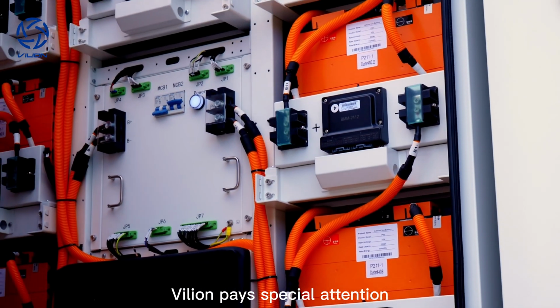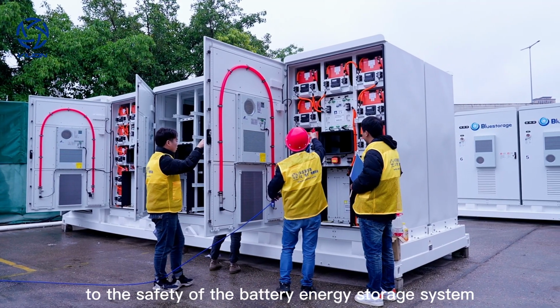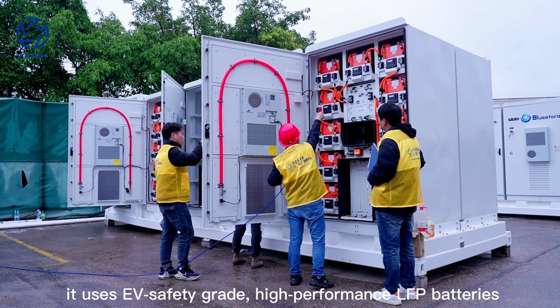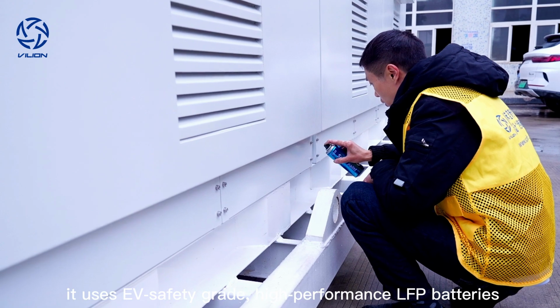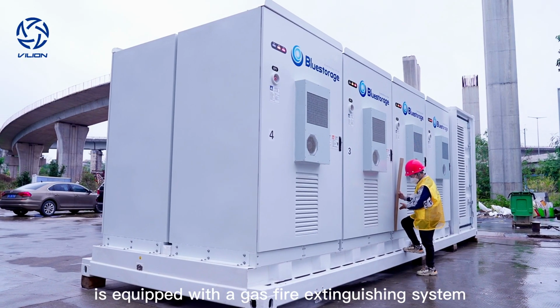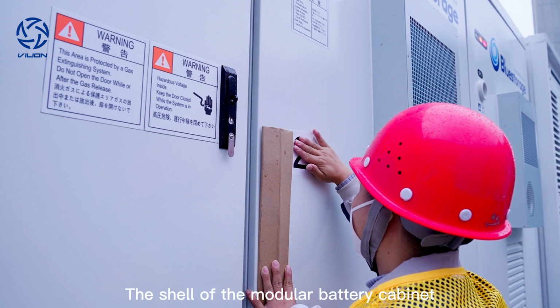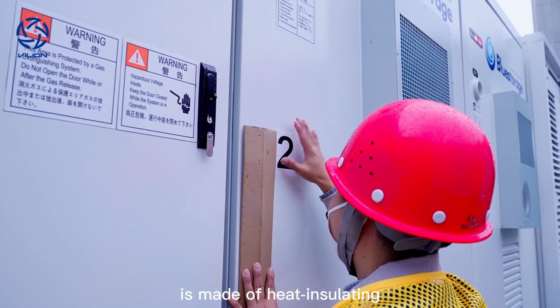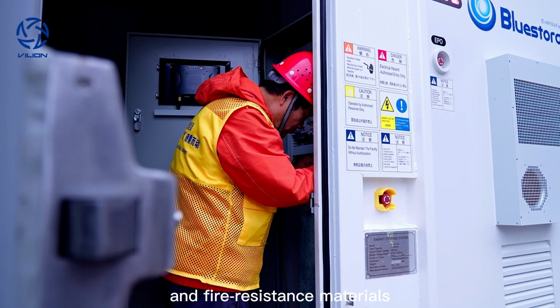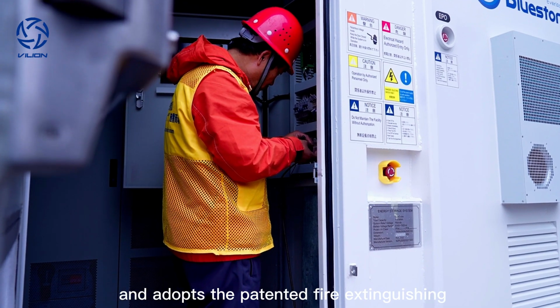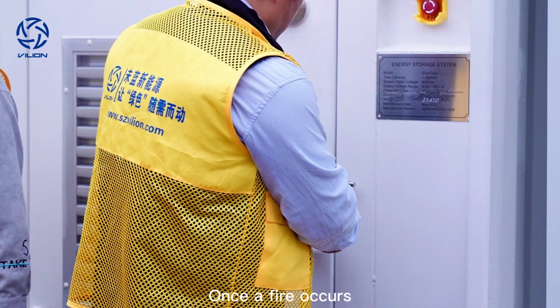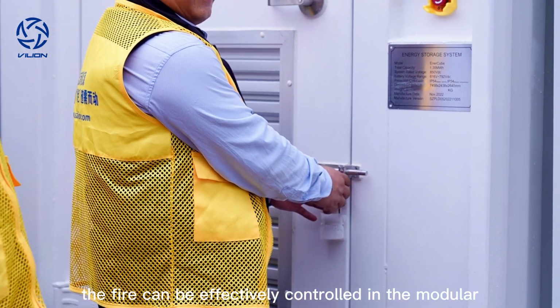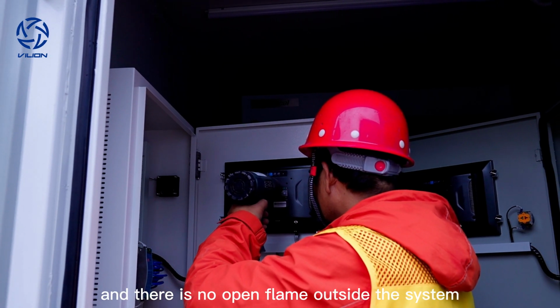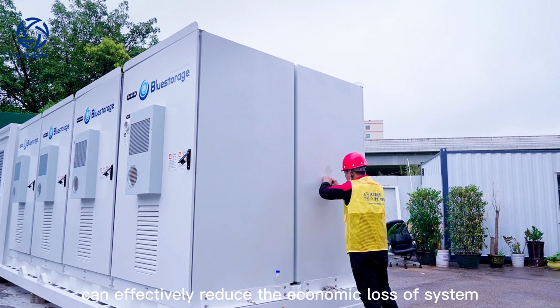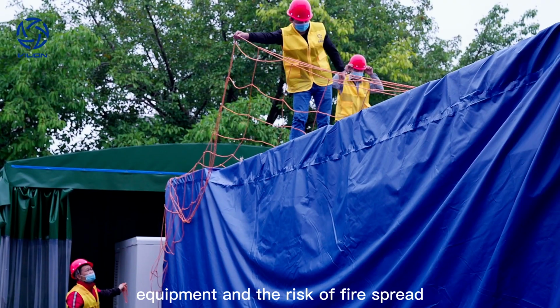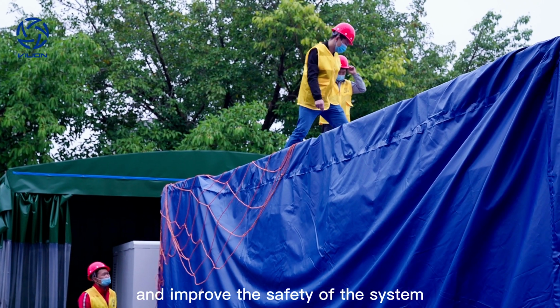Vilion pays special attention to the safety of the battery energy storage system. In terms of safety design, it uses EV safety grade, high performance LFP batteries, and the battery cabinet is equipped with a gas fire extinguishing system. The shell of the modular battery cabinet is made of heat insulating and fire resistant materials and adopts the patented fire extinguishing design of Vilion. Once a fire occurs, it can be effectively controlled within the modular battery cabinet, with no open flame outside the system, which effectively reduces the economic loss of system equipment and the risk of fire spread, improving the safety of the system.